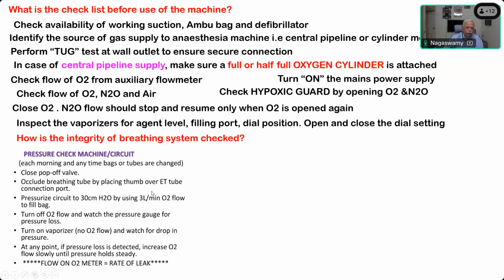Okay. So you open the oxygen flow meter to 3 liters and make sure that the airway pressure gauge shows 30 centimeters of water. Then close the oxygen flow, turn off the oxygen flow and watch the pressure gauge for pressure loss. So from 30 centimeters, if it starts dropping, that means there's a leak, or the bag also will start collapsing. It will start developing wrinkles. Then turn on the vaporizer, still with no oxygen flow, and watch for the drop in pressure. So if the drop in pressure happens without turning the vaporizer on, that means there is a leak after the flow meter.